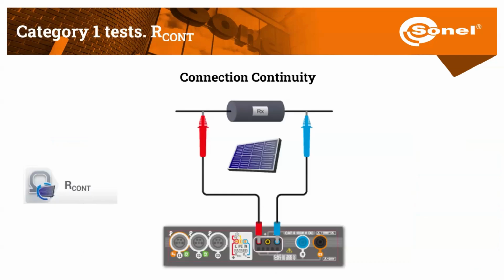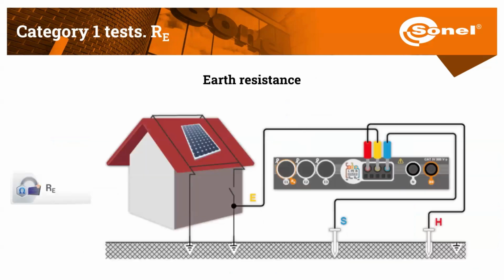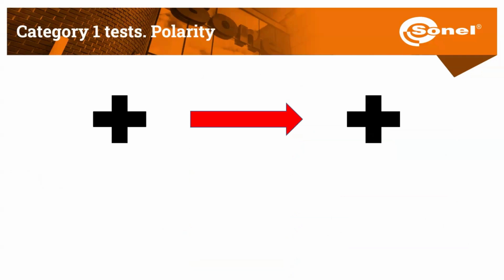Okay, category 1 tests we should make. Connection continuity, that you showed before, but I will show you a different video with this test. If the photovoltaic installation has its own grounding, the next test is to measure the grounding resistance of this system. The next test is to check the polarity. We make sure that the positive terminals are truly positive and the negative terminals are truly negative.